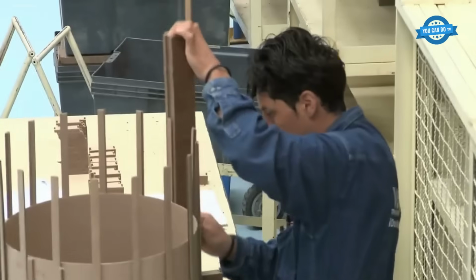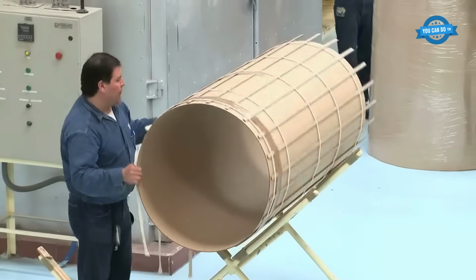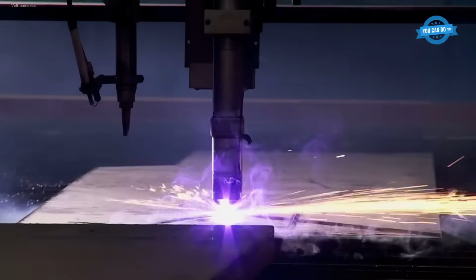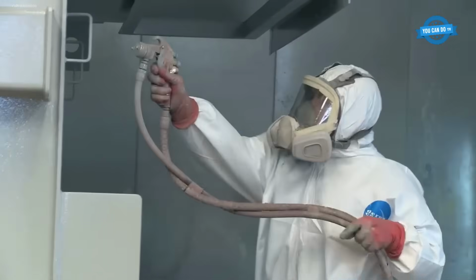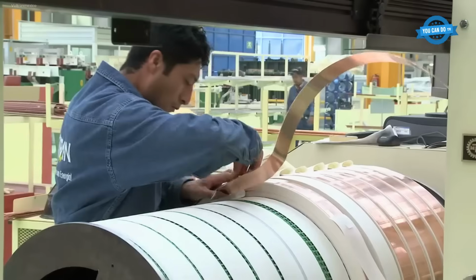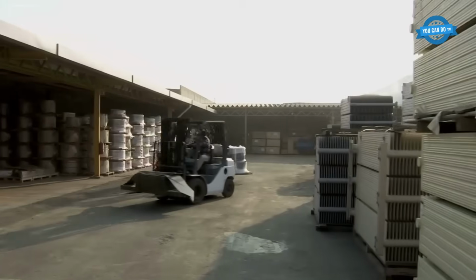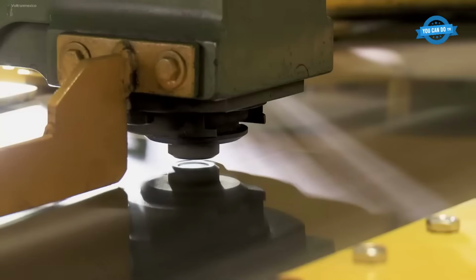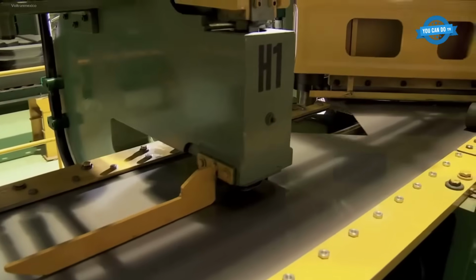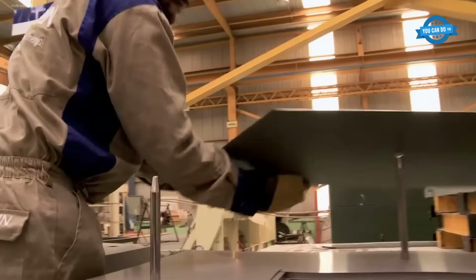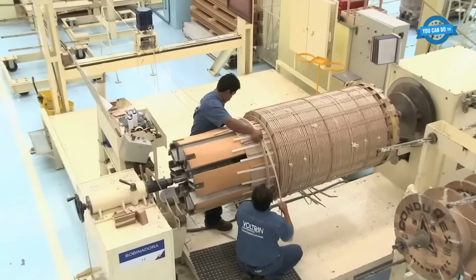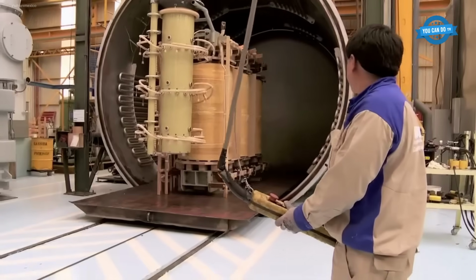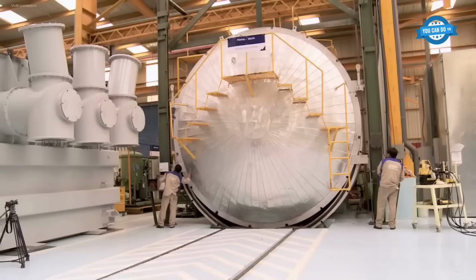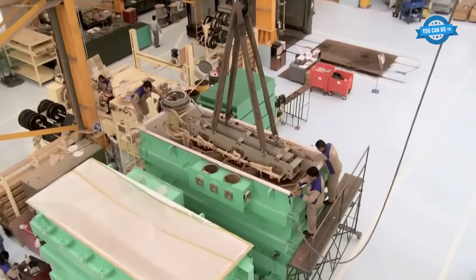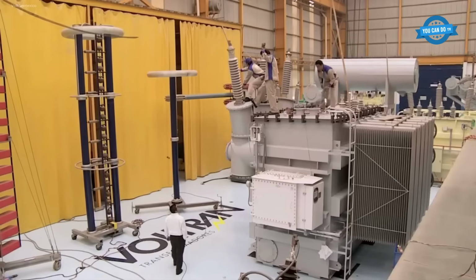Voltran specializes in the high-precision engineering and production of power and distribution transformers ranging from 150 kVA to 100,000 kVA. Key manufacturing steps include silicon steel core cutting, precision coil winding in copper, vacuum resin encapsulation, and complete dielectric testing. Final products include pedestal, substation, dry type, and resin encapsulated transformers. All systems are optimized for performance, durability, and grid efficiency.